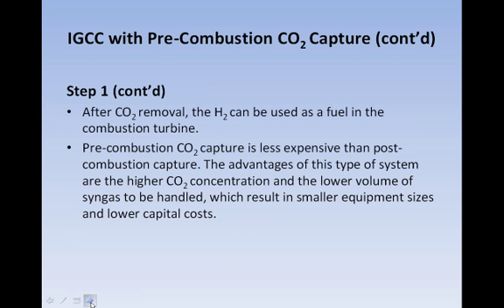After removal of the CO2, the H2 can then be used as a fuel in the IGCC combustion turbine. Pre-combustion CO2 capture is less expensive than post-combustion CO2 capture. The advantages of this type of system are the higher CO2 concentration and the lower volume of syngas to be handled in extracting the CO2. This would result in smaller equipment sizes and lower capital costs.